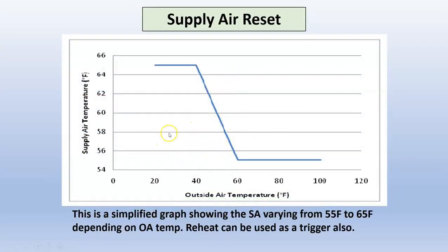Supply air reset, obviously, as it gets warmer or colder outside, I don't need 55-degree supply air temperature. I can start cranking that down. And especially on systems that have VAV heaters, you don't want them to run if you don't have to. They're typically electric resistance. Sometimes they're hot water. But by using this and cranking up that supply air, I'm accomplishing a couple of things. I'm allowing that reheat to be dropped or not used as much. And I'm allowing my chilled water temperature to be increased, which is a big saver there. So I'm saving energy on a couple of fronts.